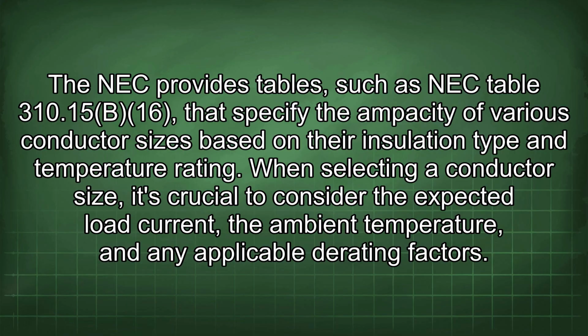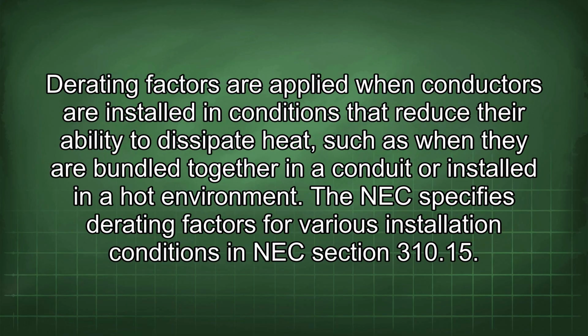When selecting a conductor size, it's crucial to consider the expected load current, the ambient temperature, and any applicable derating factors. Derating factors are applied when conductors are installed in conditions that reduce their ability to dissipate heat, such as when they are bundled together in a conduit or installed in a hot environment. The NEC specifies derating factors for various installation conditions in NEC section 310.15.